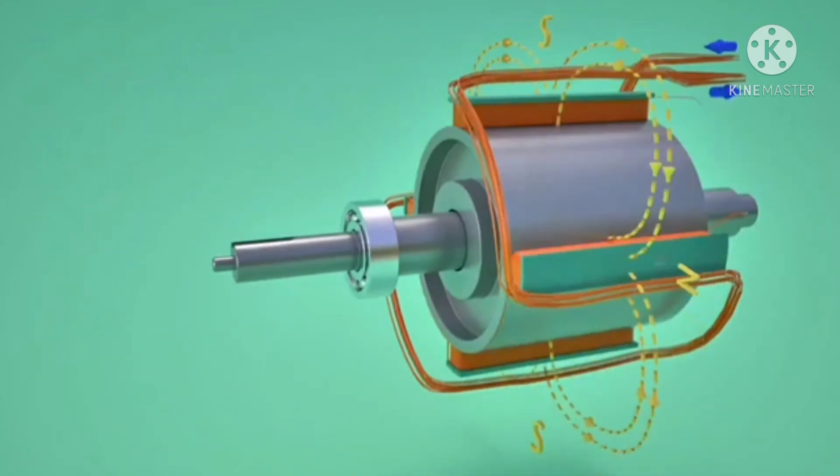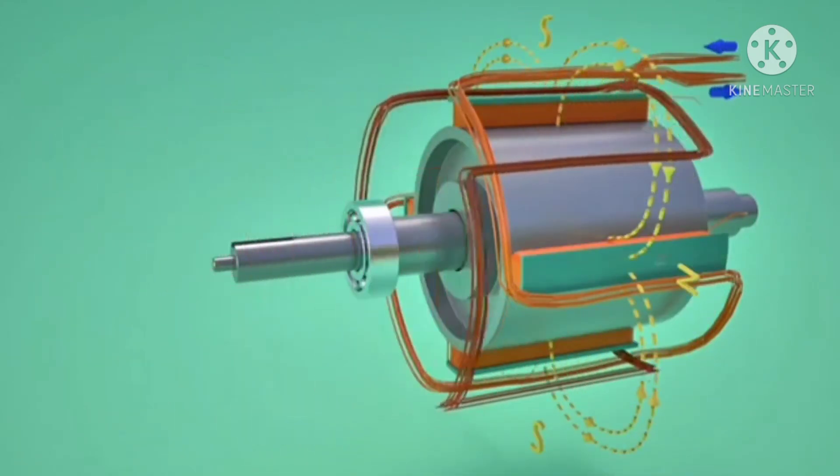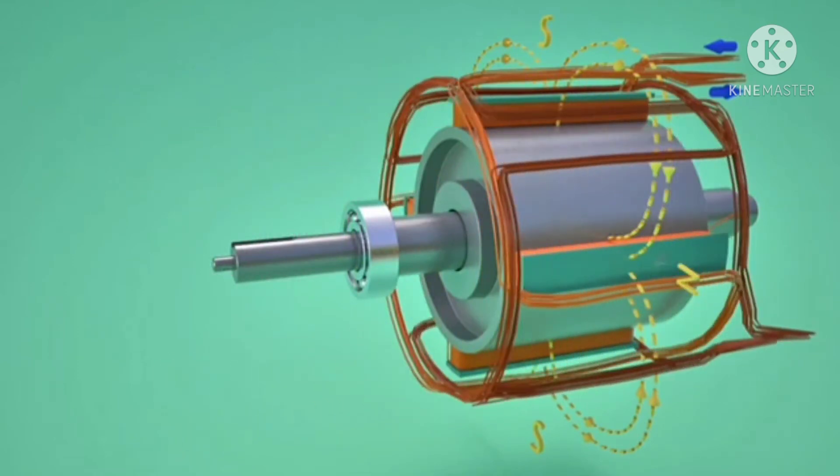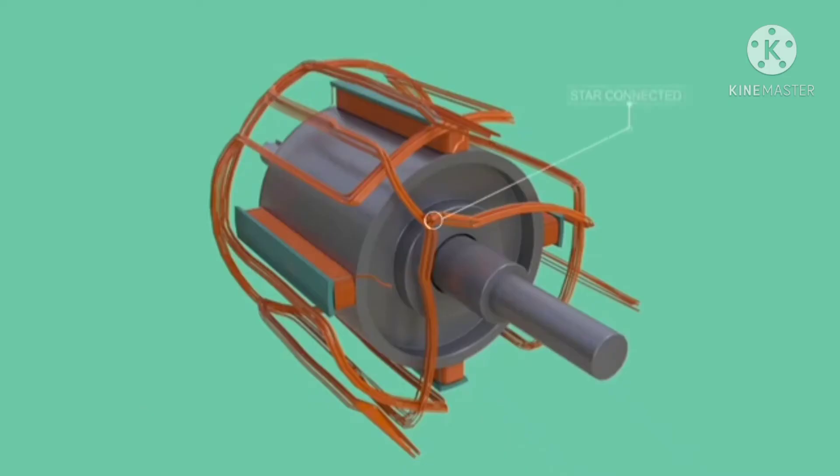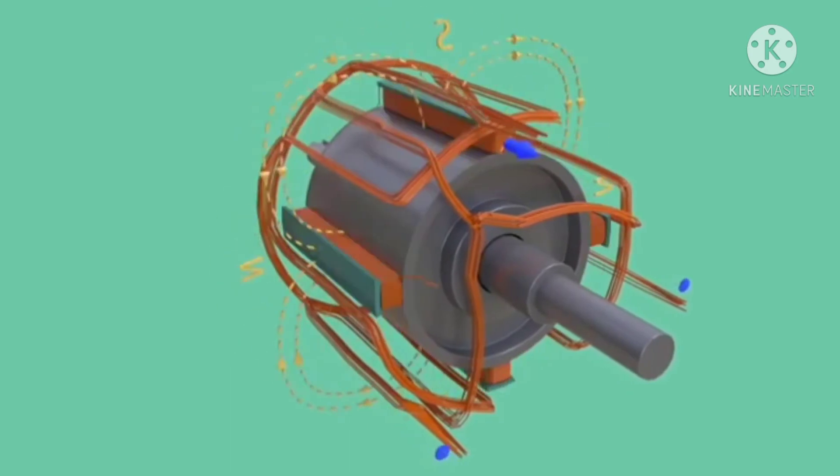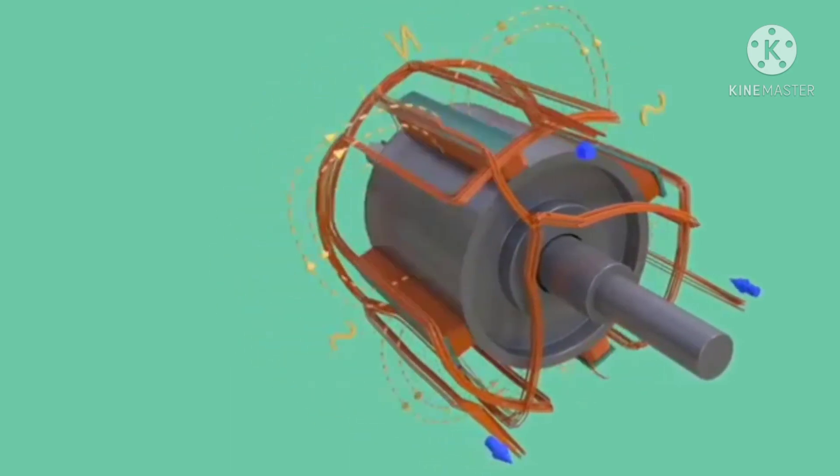For producing three-phase AC current, two more such armature coils which are in 120-degree phase difference with the first are put in the stator winding. Generally, one end of these three coils are star connected, and three-phase electricity is drawn from the other ends. Neutral cable can be drawn from the star connected end.